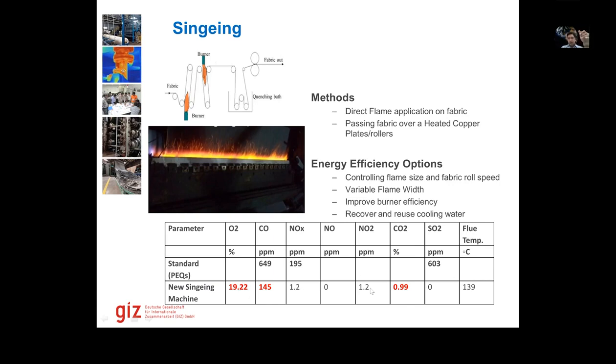If we control the oxygen quantity and maintain the air-fuel ratio, that's where we can improve the flue gas temperature - carbon dioxide very low and oxygen very high are signs to look at. How do we control the oxygen and CO2? How do we measure it? Is there a sensor, or how do we do that?